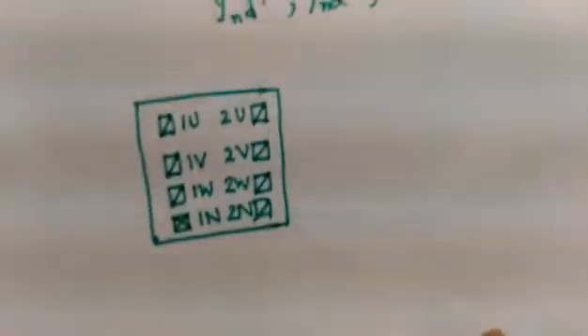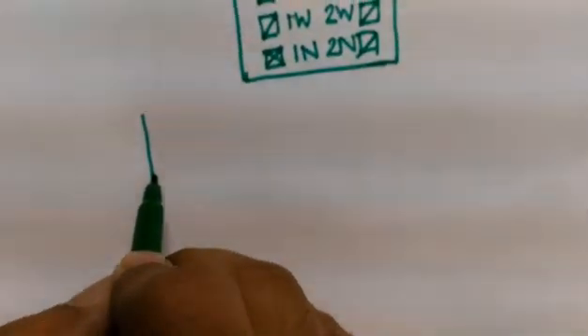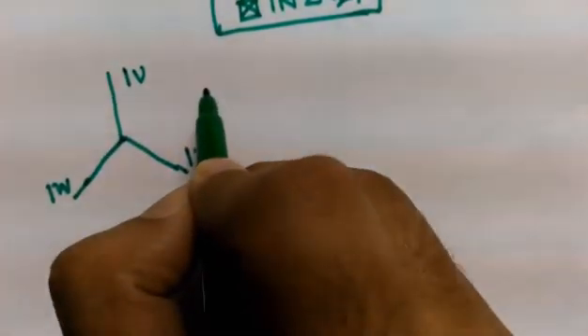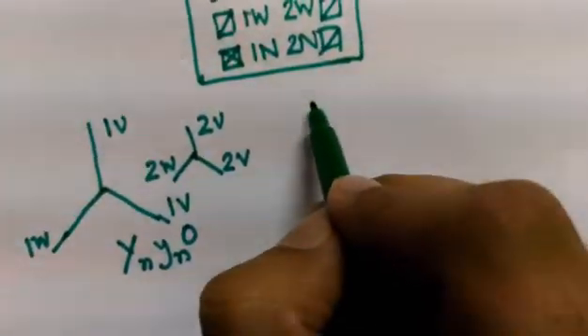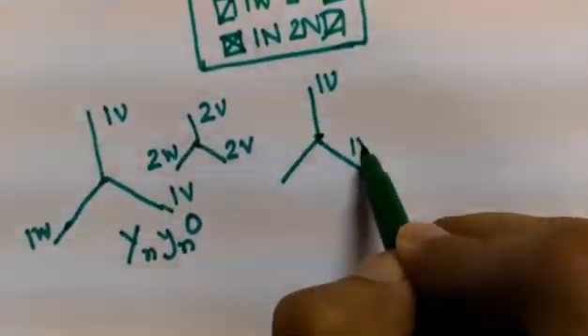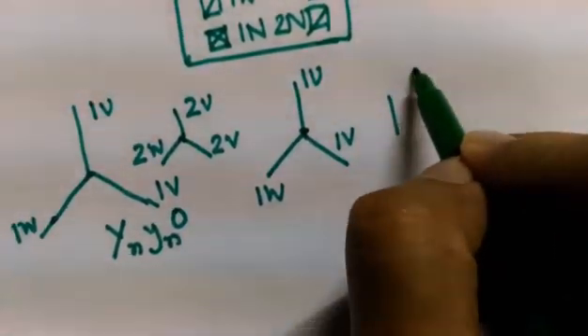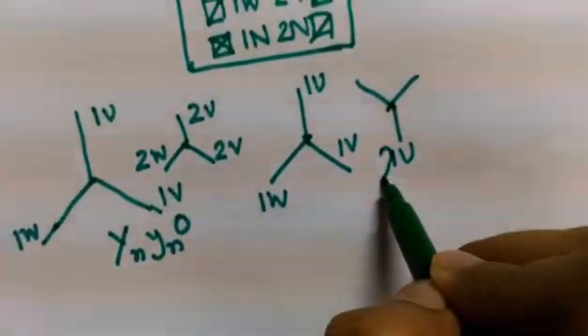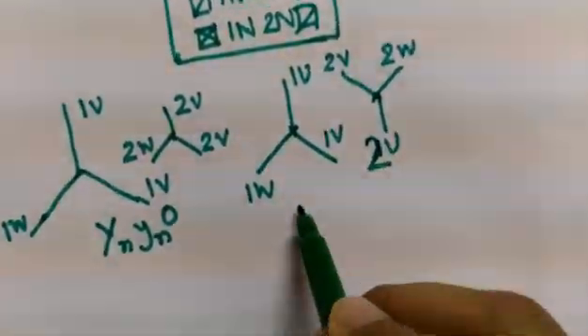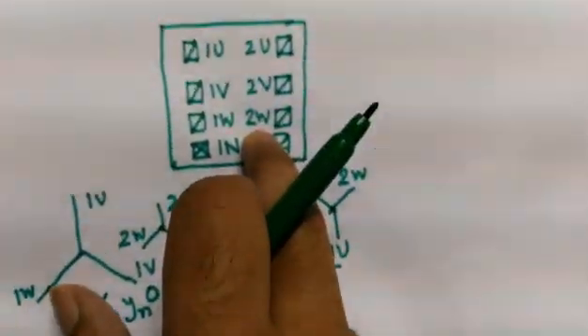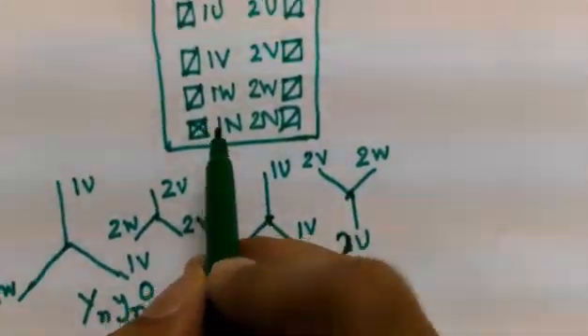For YnYn0, the vector group looks like this: 1U, 1V, 1W on the primary side, and 2U, 2V, 2W in phase with the primary — this is your YnYn0 vector group. For YnYn6, the secondary vectors 2U, 2V, 2W are displaced by 180 degrees — this is your YnYn6 vector group. Now we will determine which type of vector group this transformer has.